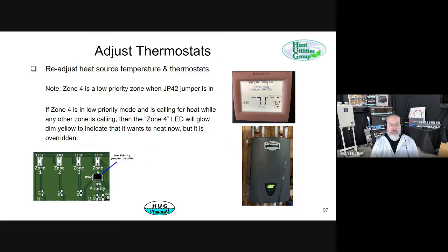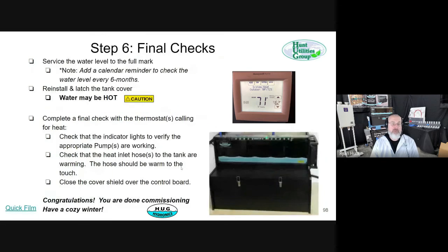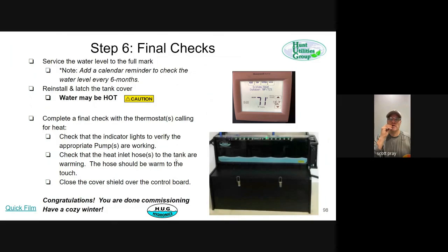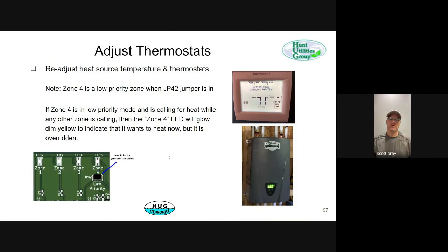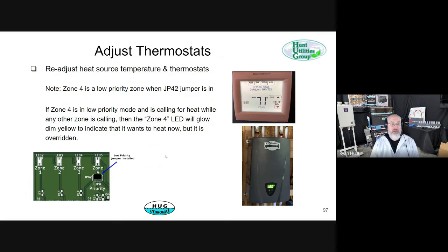So that's an option that people would ask for, and we made it happen, and it's optional to use or not. What's that used for? Because I think that's important for me. Yeah, so it's if you have a low priority zone where it's okay if it only gets heat when all the other zones are happy. As long as all the other zones are satisfied, then it can turn on zone 4. Without the low priority jumper in place, zone 4 will turn on whenever the thermostat asks for it.